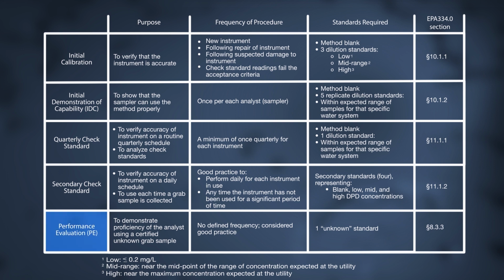Performance evaluation, or PE, is a test of unknown certified standards measured by an analyst to demonstrate the proficiency of the analyst. Method blank is an analyte-free matrix or deionized water to which all reagents are added in the same volumes or proportions as used in standard measurements. It is carried through the complete sample preparation and analytical procedure. The method blank is used to account for interferences or contamination resulting from the analytical process. Dilution standard. A chlorine dilution standard is a NIST concentrated primary chlorine standard diluted to an appropriate concentration.